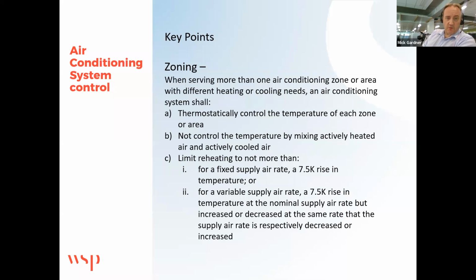So key points for zoning. Where you're serving more than one zone or area, you have to be able to thermostatically control, not control it by mixing actively heated air and actively cooled air. And there's an item here about limiting reheats to not more than 7.5 Kelvin rise in temperature. That's going to be an interesting one, because a lot of the time when we put air in, particularly if using like a VAV system, we can end up increasing that temperature a lot more than that. So this system here is saying that actually we can't be doing that.